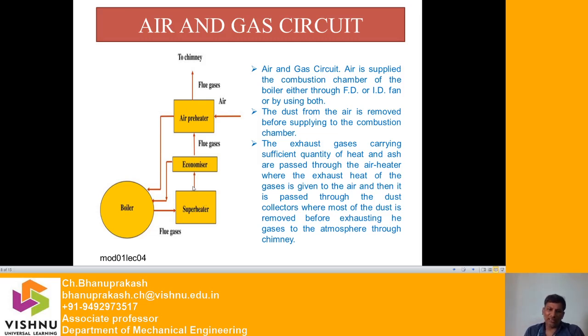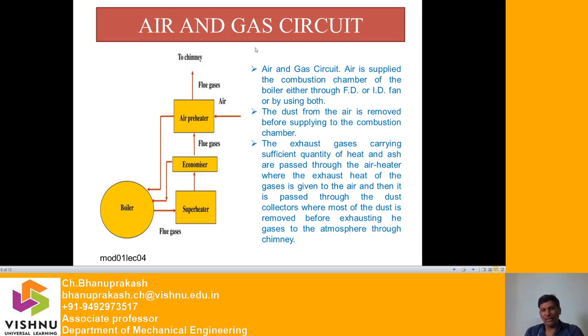The exhaust gases then pass through the economizer, where feed water absorbs heat from the flue gases. Next, these flue gases pass through the air preheater, where air taken from the atmosphere absorbs heat from the flue gases, gets heated, and is then fed back to the boiler — the cycle continues. After passing through the air preheater, the flue gases pass through the chimney and are finally released to the atmosphere. Before release, flue gases containing dust or ash particles are passed through a cyclone separator or dust collector to remove all dust and ash particles.